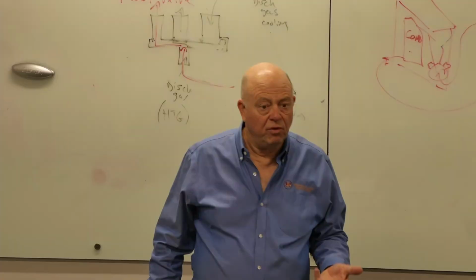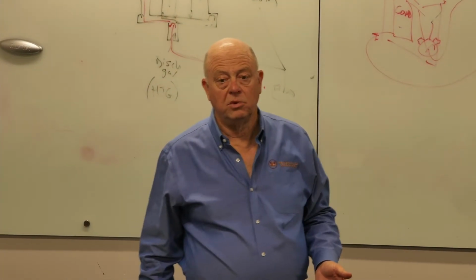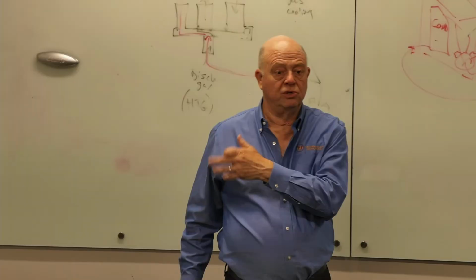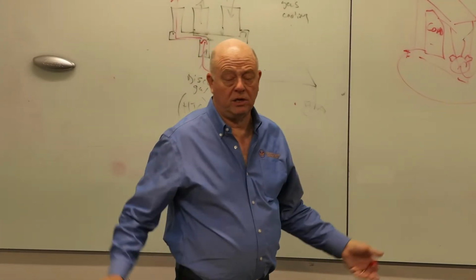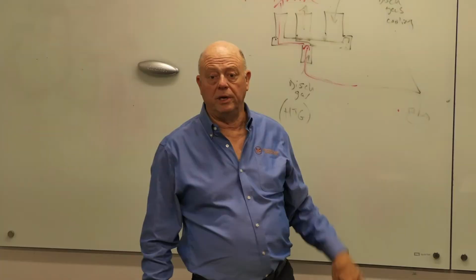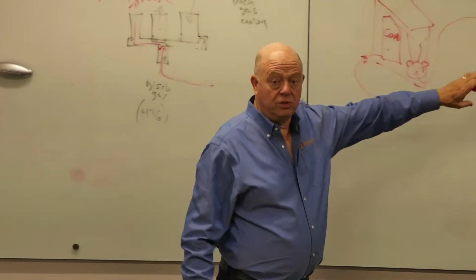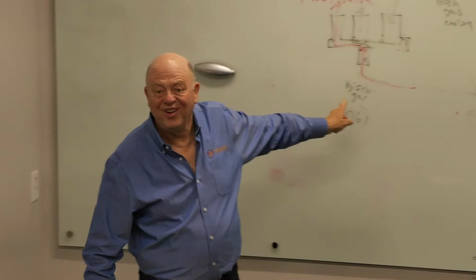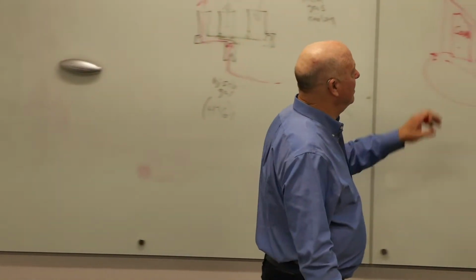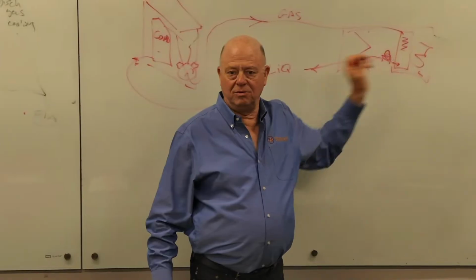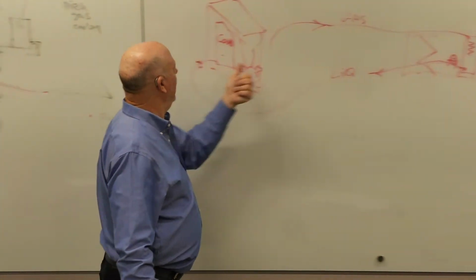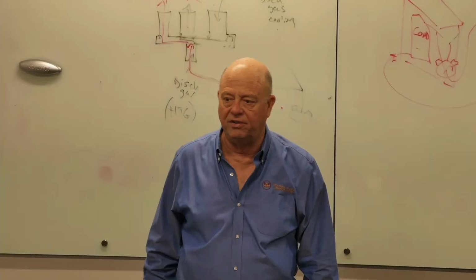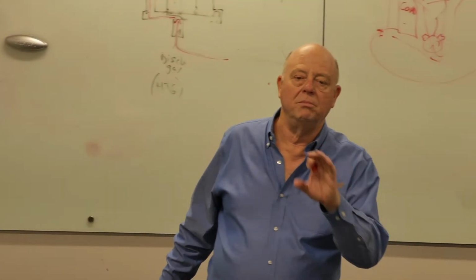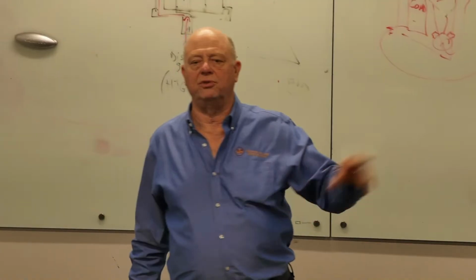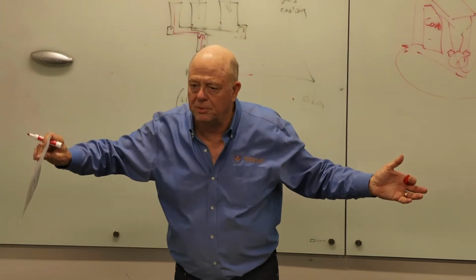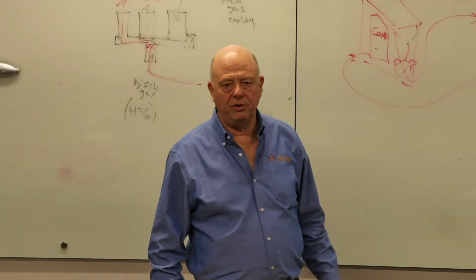So a heat pump will have a defrost mode. So does every major commercial freezer and walk-in cooler and stuff like that, because they have 24/7 modes and it can be cold at night. And what they do is they reverse the valve and they spend a period of time going back to normal air conditioning operation, and now they're putting hot gas through here and they melt all the frost off. And they have some combination of time and temperature sensors to decide when they think they've accomplished that purpose, and then they go back to normal operation.